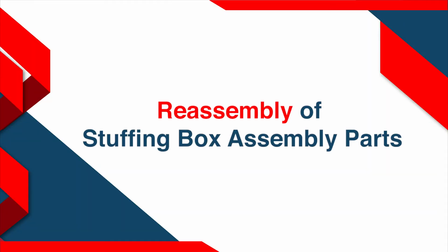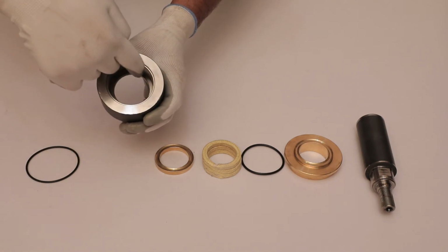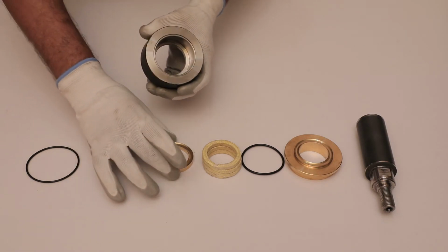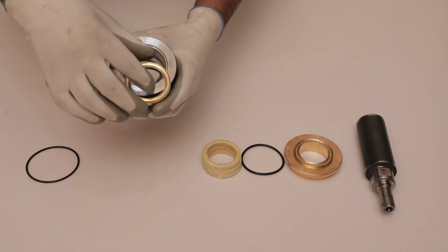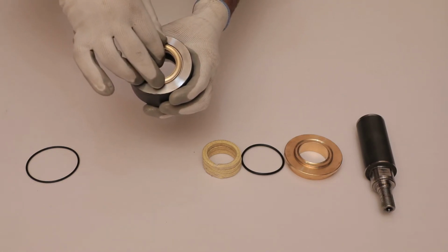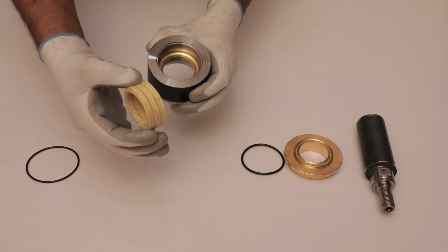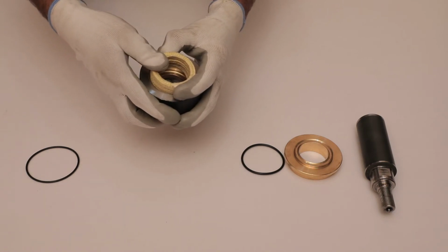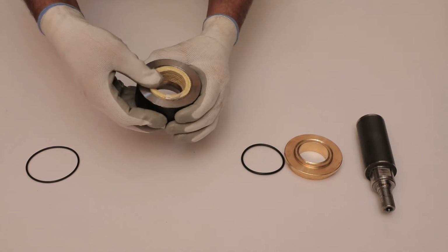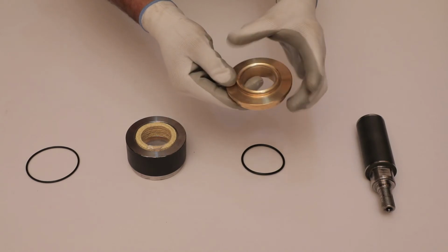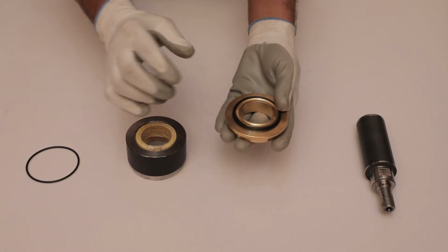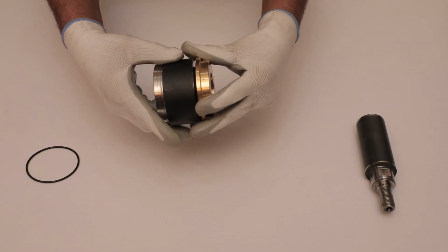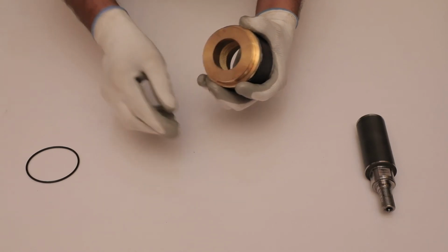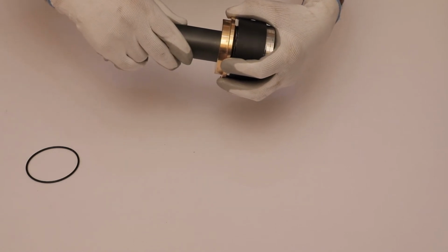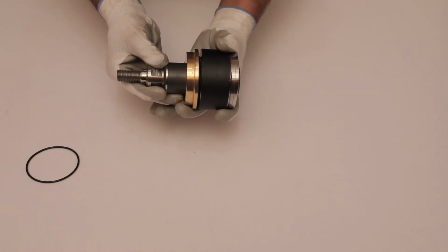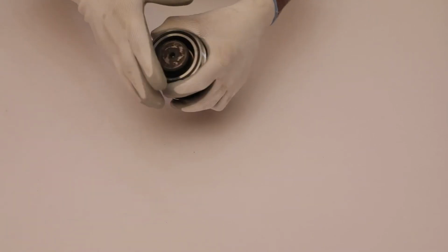Reassembly of stuffing box assembly parts. Take the stuffing box and assemble the inner support ring in the stuffing box, facing flat surface of inner support ring downward. Then softly put plunger seal and push so it can take its proper position. Put the O-ring on its position of the outer support ring and place the outer support ring on the stuffing box. Install plunger inside the stuffing box and keep threaded portion from outer support ring. After that, place the O-ring on its groove of the stuffing box.